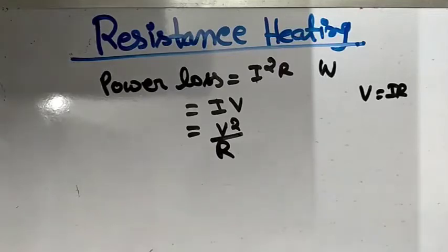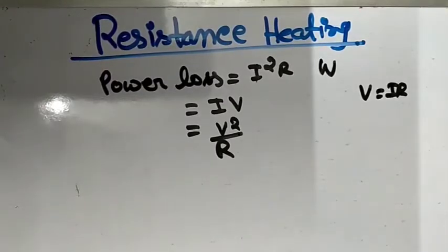And in addition to above, resistance heating method is favored on account of uniform power demand, giving a good load factor and almost unity power factor. Okay, so this is all about resistance heating. This is the basic concept of resistance heating. Now I discuss about direct resistance heating.